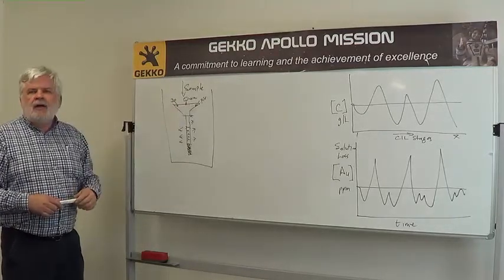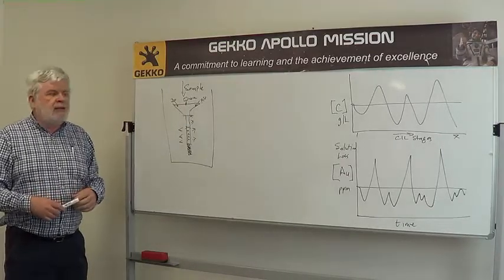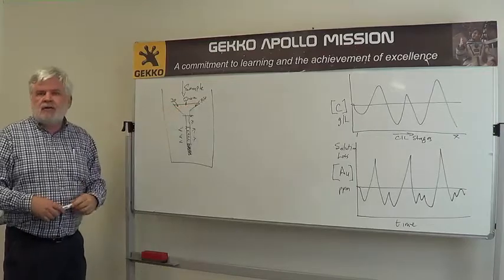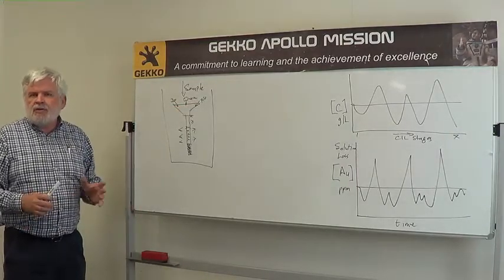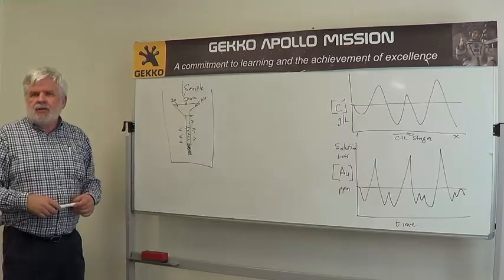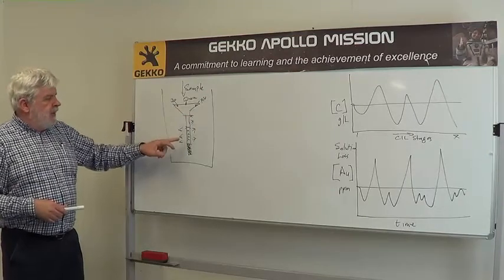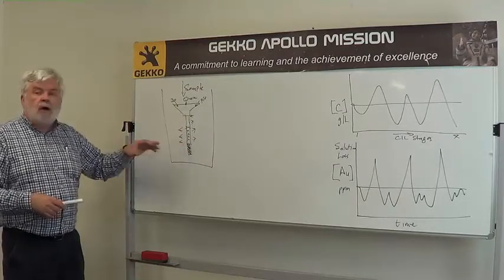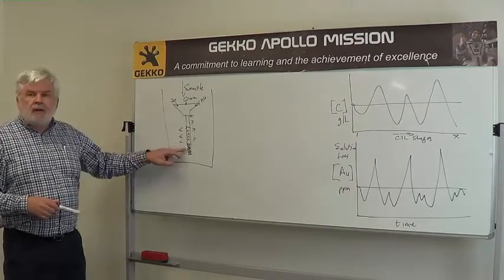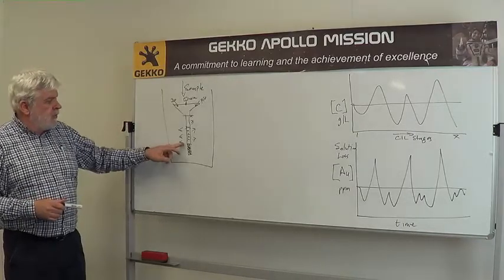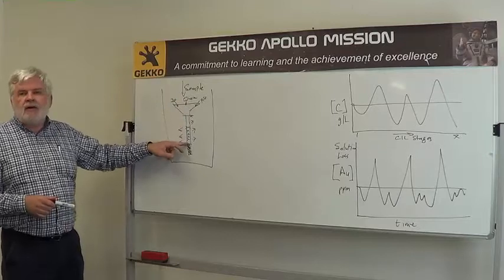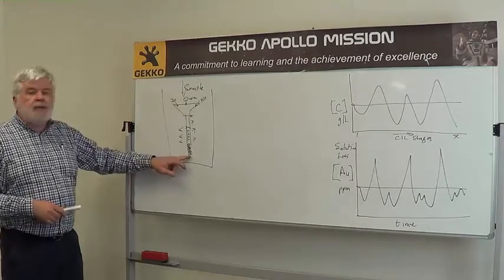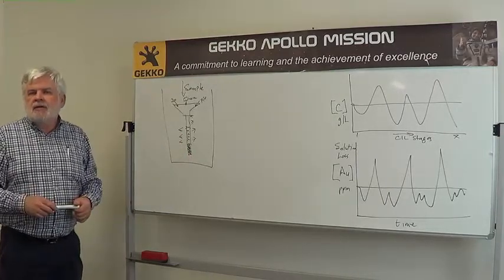We fill the cone — it has a level indicator — and when the level indicates the sample is collected, we first measure dissolved oxygen and pH in that solution before even measuring carbon. So we're measuring DO, dissolved oxygen, and pH right down the circuit. We then open a valve and the sample flows through a strainer or sieve; the pulp is removed with washing and the carbon is left as a column at the bottom of the strainer. We use a laser to measure the height of that carbon column, and from that height we get a volume, and from that volume we get a carbon concentration. A small valve then opens, the sample is washed out, and we move on to the next tank in the series.